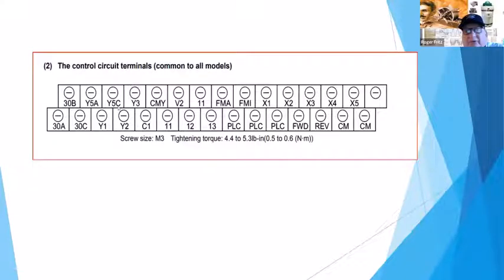These are all outputs. You've got your C1, which is your 4 to 20 milliamp input. Again, go back to the normal common of the circuit. You've got here a frequency meter, analog output, current output, and then various extra terminals like on a PLC. So what's in all of the programming of those drives is how to control how all of these functions work.